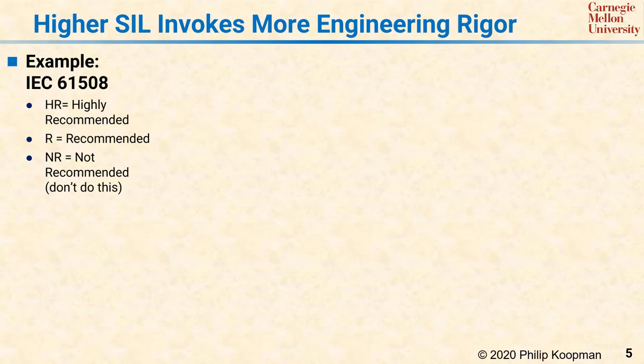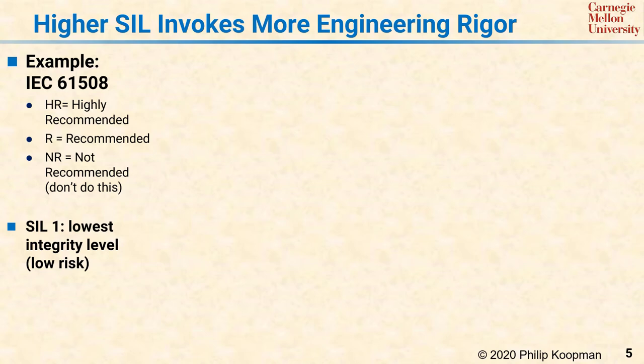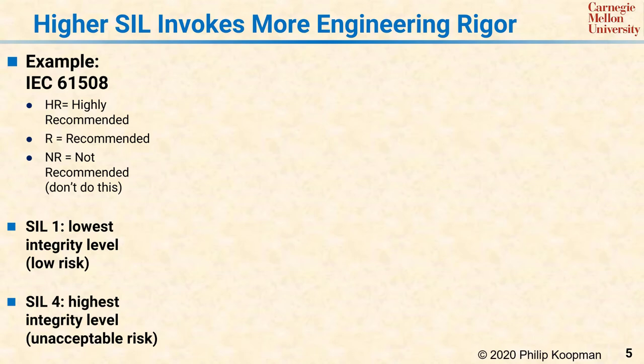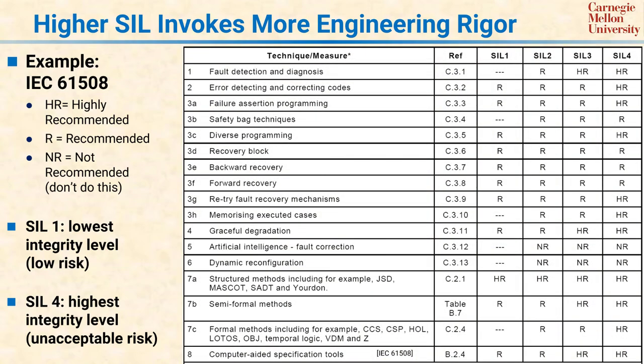As mentioned previously, for this safety standard, SIL 1 is the lowest integrity level and presents low risk. Generally speaking, SIL 1 systems require a reasonable level of engineering rigor but not a lot of special techniques for safety. This example table extracted from IEC 61508 shows that for SIL 1, a number of techniques are recommended, but only one is highly recommended — using structured methods for writing the code.